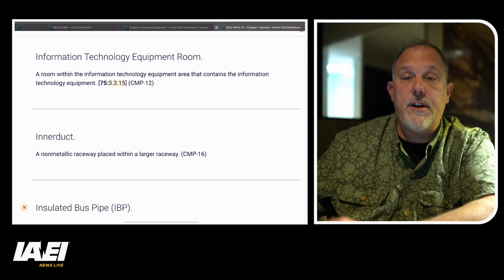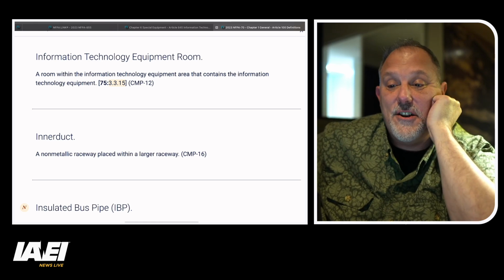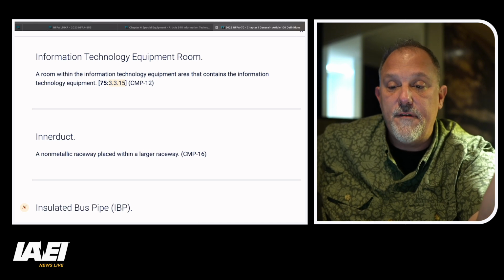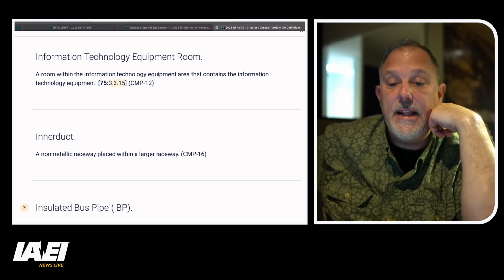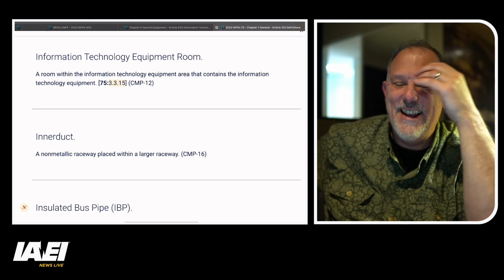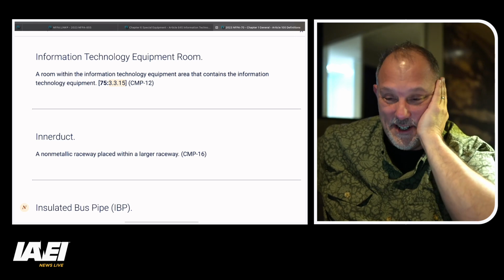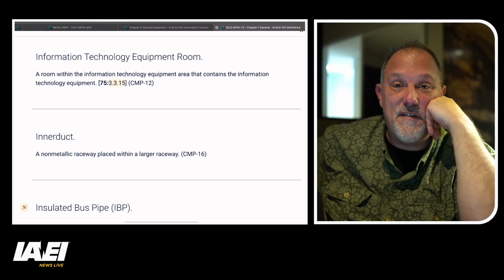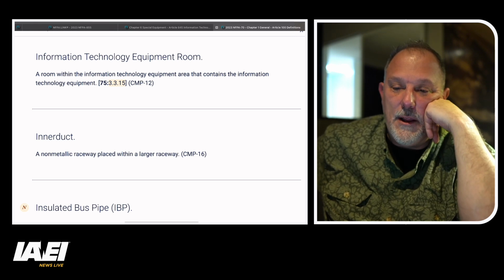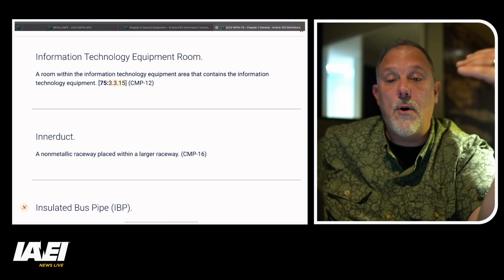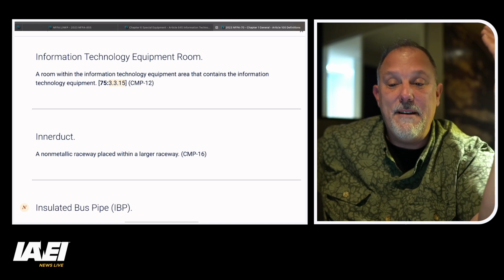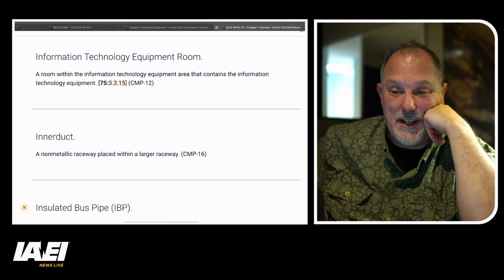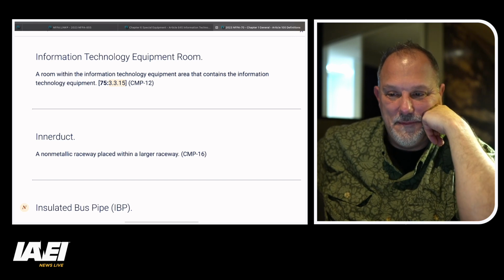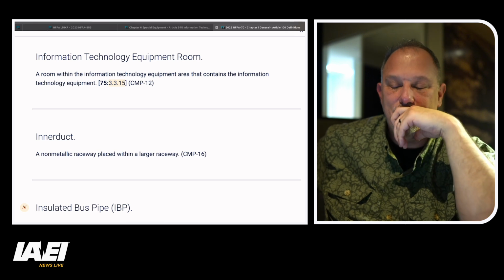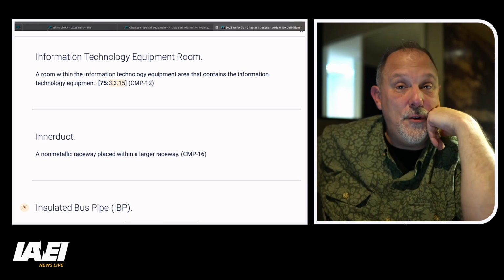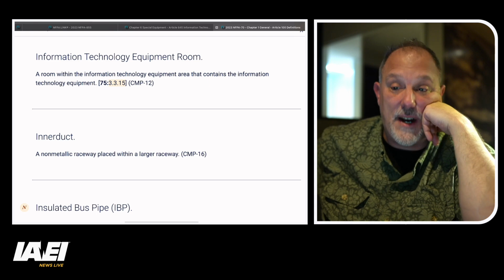Because it comes out of NFPA 75, that tells me that if you're working on an information technology equipment room, which is a room within the information technology equipment area that contains the information technology equipment. Oh, wow. I'm sorry, I didn't mean to laugh, but that was funny. Anyway, it's out of NFPA 75, so if you are working on equipment that meets this definition, then you need to understand what's in NFPA 75.